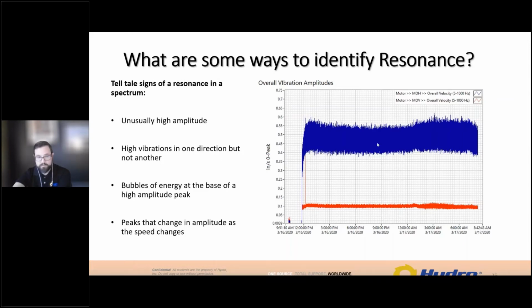The second cue is high vibrations in one direction but not the other. You can see here on this trend plot, showing on the motor outboard the horizontal direction and the vertical direction of vibration, there's a huge difference from horizontal to vertical. That kind of highly directional vibration is oftentimes going to be present in a resonance situation. The next one that we'll talk about is bubbles of energy. We'll show you what that means, but sometimes the shape of the spectrum can give you an indication. And the last thing I'll show you is if you have changing speed and you have amplitude changes that result, you can have a tip-off that resonance could be involved.